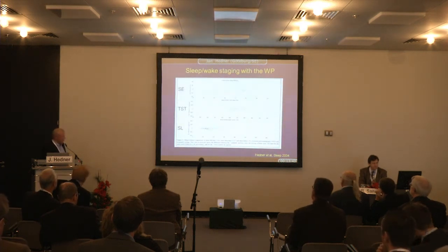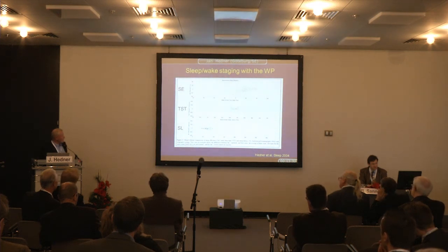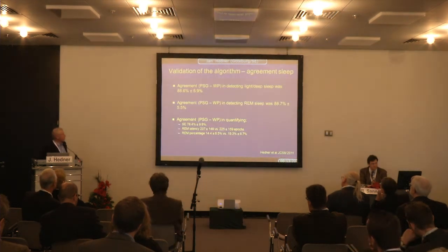If you look at the sleep-wake staging, it's probably hard to see for some of you at the back. If we look at sleep efficiency, total sleep time, and sleep latency in these Bland-Altman plots, you can see that we have mean values and variability going down this range, and an overall judgment would be, yes, they look pretty good, or reasonably well.